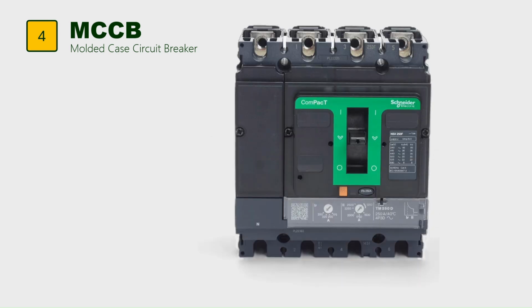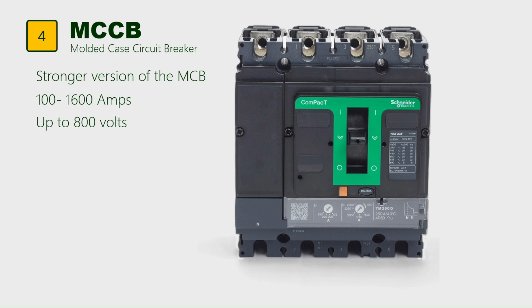The MCCB, or Moulded Case Circuit Breaker, is like a stronger version of the MCB. It handles higher currents from around 100 amps up to 1600 amps and can work at voltage up to 800 volts. MCCBs can also be fitted with motorized mechanisms, which means you can open and close them remotely. This is useful in factories, large buildings, or anywhere the breaker is part of an automated system.